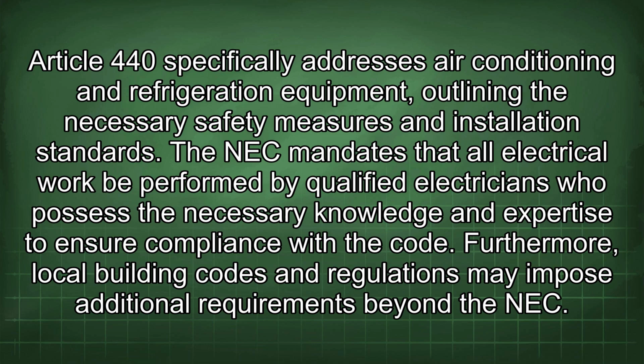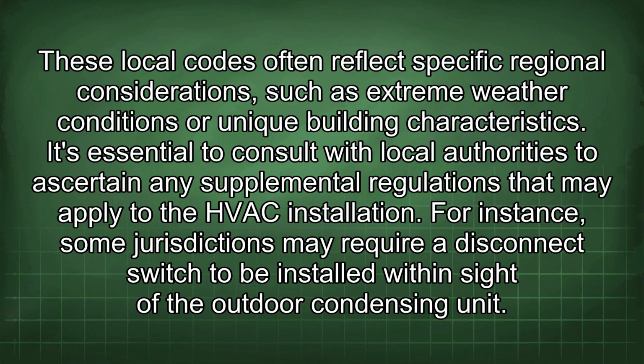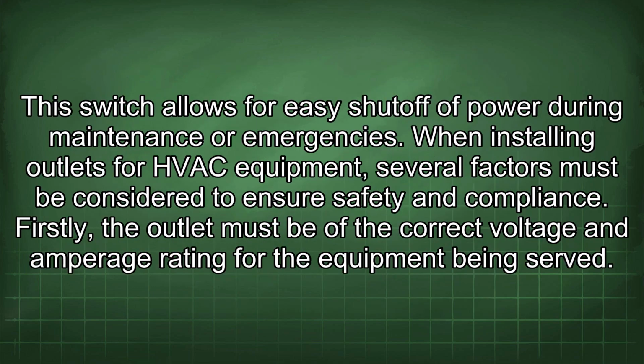Furthermore, local building codes and regulations may impose additional requirements beyond the NEC. These local codes often reflect specific regional considerations, such as extreme weather conditions or unique building characteristics. It's essential to consult with local authorities to ascertain any supplemental regulations that may apply to the HVAC installation. For instance, some jurisdictions may require a disconnect switch to be installed within sight of the outdoor condensing unit. This switch allows for easy shut-off of power during maintenance or emergencies.